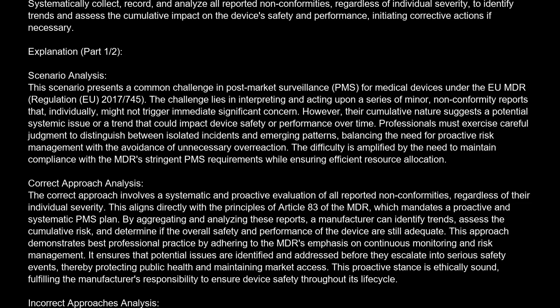Correct answer is C. Systematically collect, record, and analyze all reported nonconformities, regardless of individual severity, to identify trends and assess the cumulative impact on the device's safety and performance, initiating corrective actions if necessary.